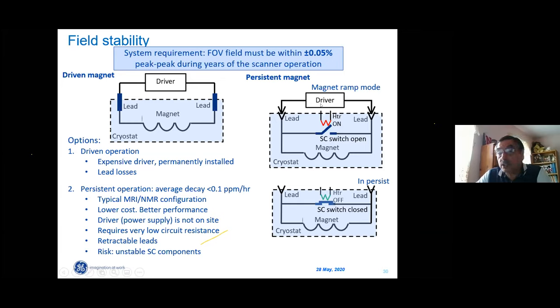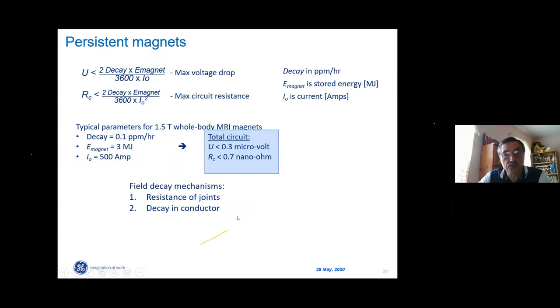Advantages are, we don't even need a driver. Actually, our service technician comes with a driver. So MRIs are not equipped with drivers. The challenge for us, for the superconductivity industry, is that we need very low resistance of this circuit. Let us estimate what should be the resistance of this circuit in order to deliver the required uniformity. The total resistance of the circuit should be less than 1 nanohm total. 1 nanohm, 10 to minus 9. Just compare, if we make just a good copper to copper joint, its resistance is 10 to minus 8.